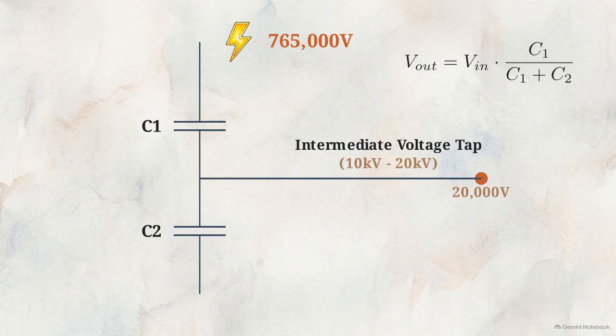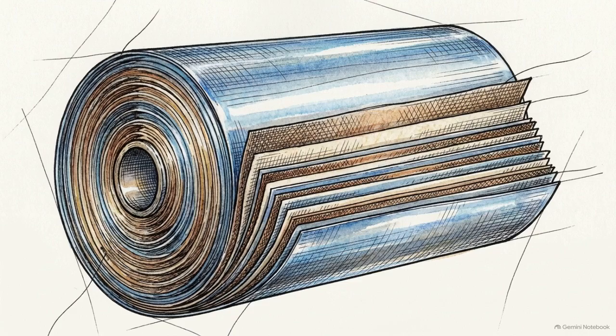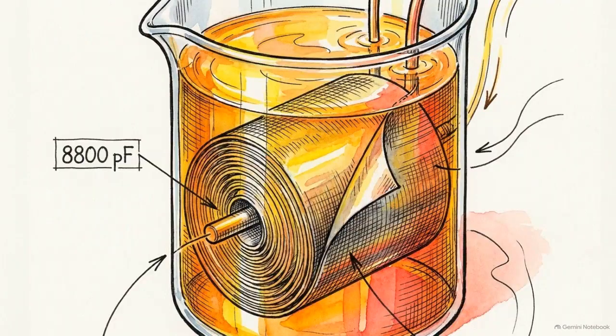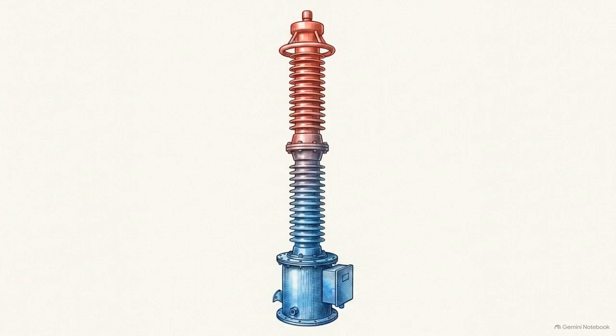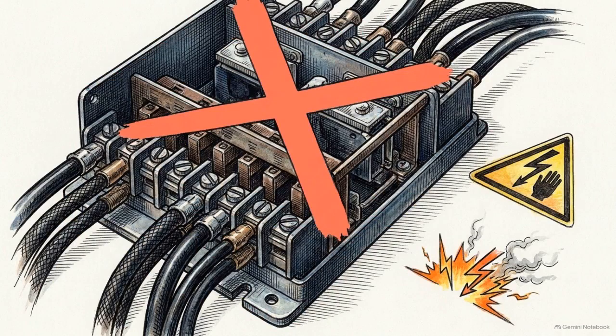To handle the electrical stress without shorting, these capacitor elements are made of alternating paper and polypropylene foil, tightly wound and bathed in synthetic dielectric oil, to yield a total capacitance of 8,800 picofarads. This stack survives the raw grid by distributing the electrical stress along its height, but the intermediate voltage pulled from the tap point is still around 10 to 20 kilovolts, too high to feed directly into a modern protection relay.